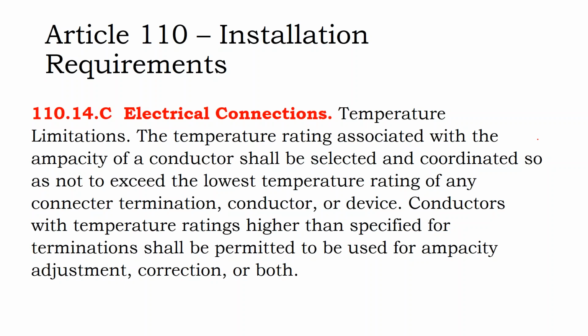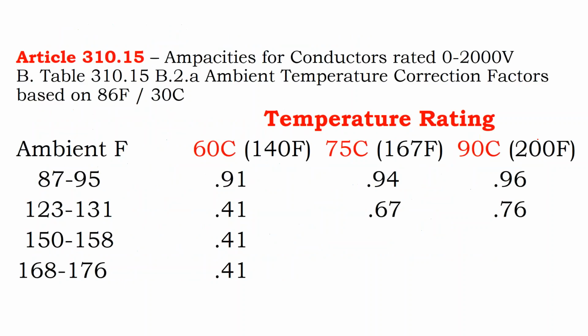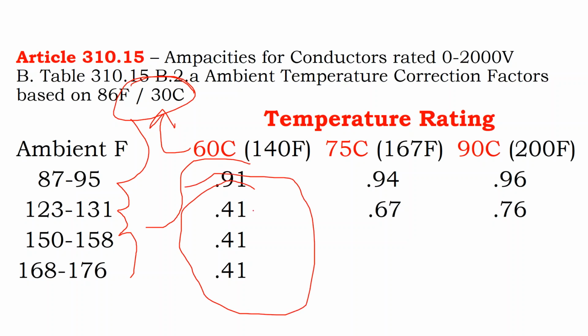Electrical connections, the temperature rating associated, yeah, so it's just a restatement of the previous slide. So when we look at a 30C, 86 degree Fahrenheit ambient temperature, and we're using 60C, 75C, and 90C wire, all of it is rated. The 60C cable can certainly withstand a 30C ambient environment. As the temperatures begin to climb, the cable has to be substantially derated and essentially carry less electricity than it could at lower temperatures, so that the combined effect of the internal temperature of the wire does not heat up to the point where it causes a fire by getting too hot, not because it's arcing electricity into the building or structure. It's just heating up, and that heat is starting a fire.